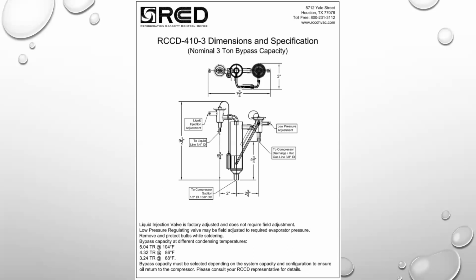Another thing I would like you to notice is that it says low pressure adjustment. Yes, that is on a valve coming from the hot gas line, but you're adjusting your saturated suction, low pressure at that point. Also, you'll notice the compressor discharge line, liquid line, and the suction connection down there.